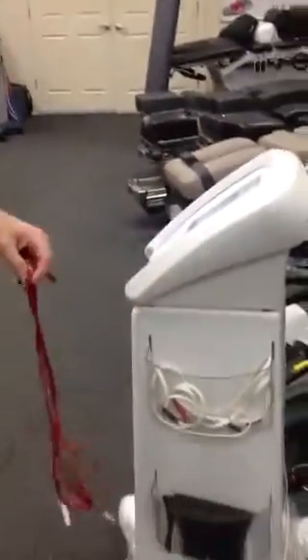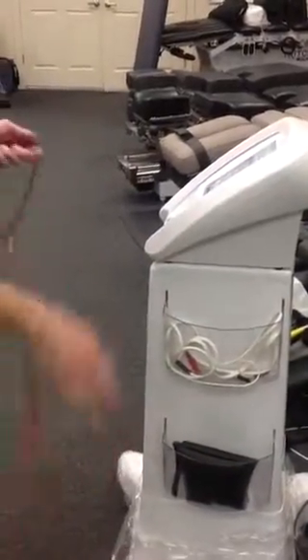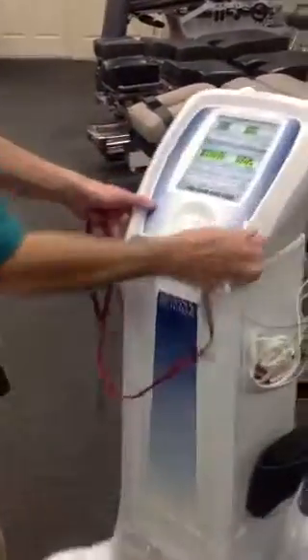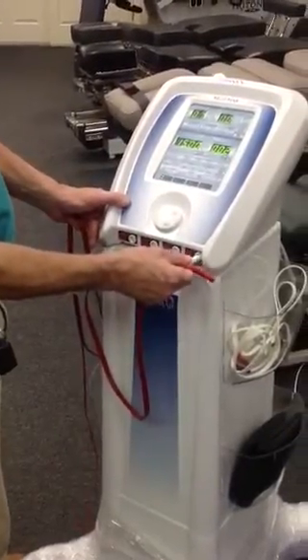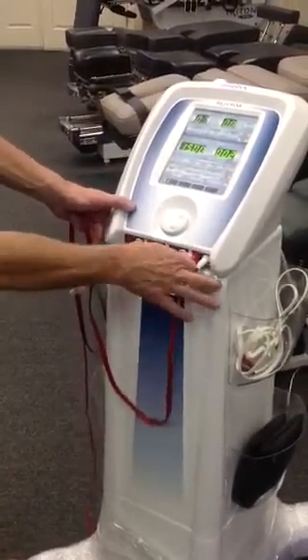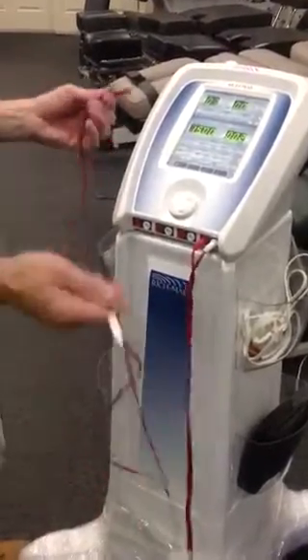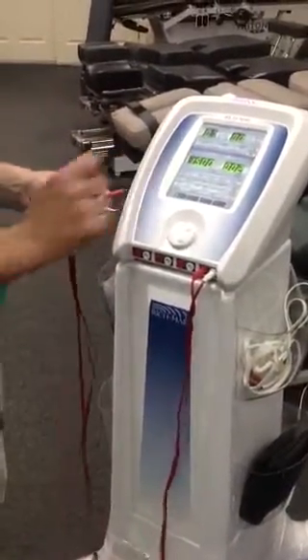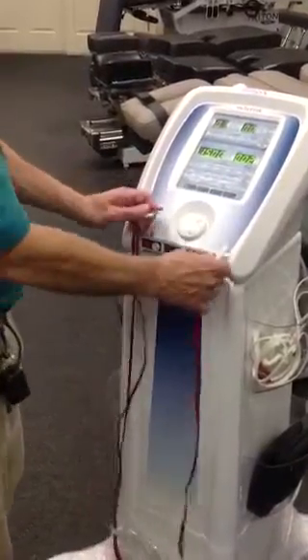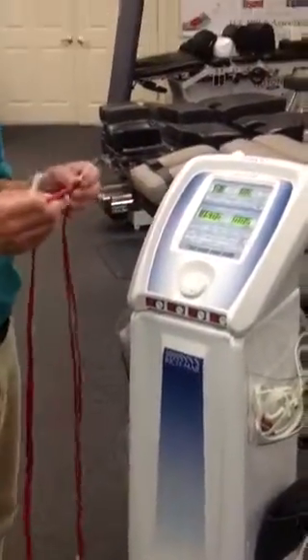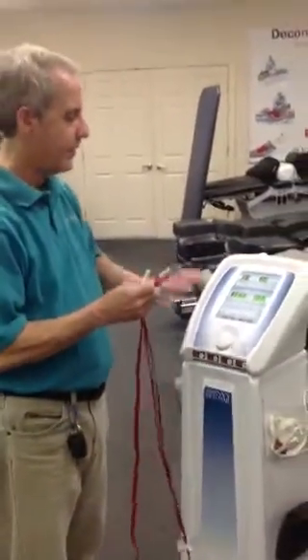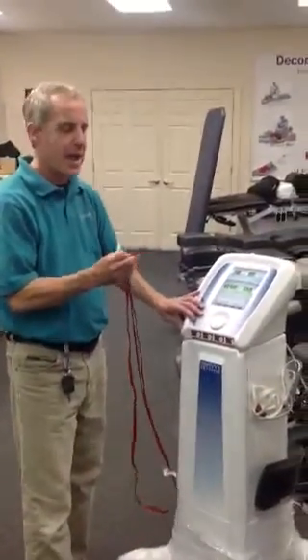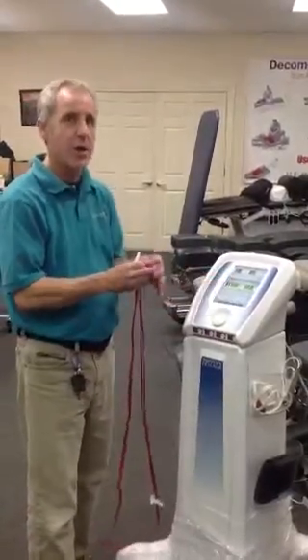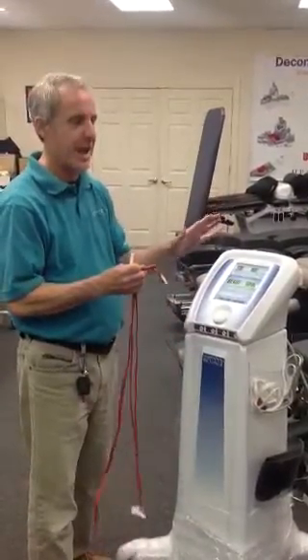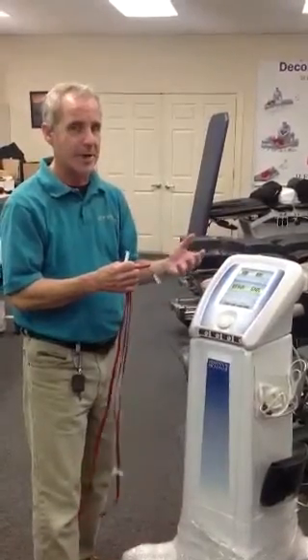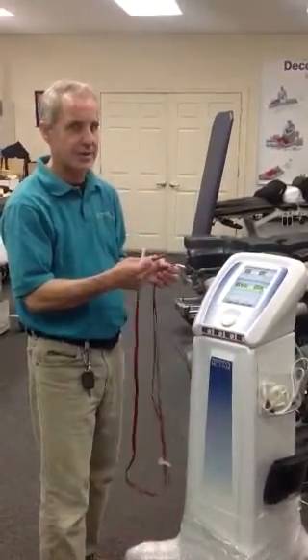Alright, so one more thing I'm going to show you in this short video is this is a pair of your lead cords, and your lead cords certainly go into the front as the white goes in the white. There we go, and the red goes in the red, and they split apart, and you have your basic sticky electrode that would go on either side. But if your machine ever surges on anybody and you're questioning whether it was the machine or the lead cord or the sticky pad, the easiest thing to do is to swap out a pair of sticky pads and try it on yourself, see if it works.